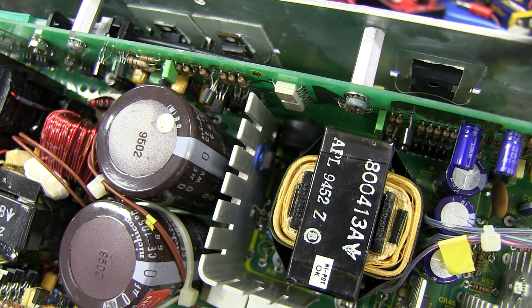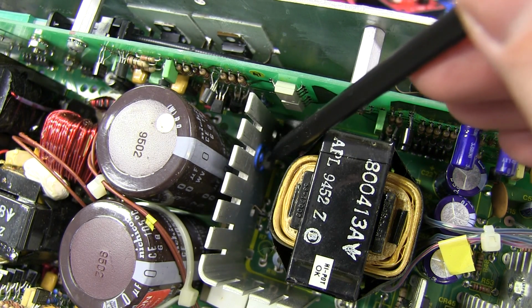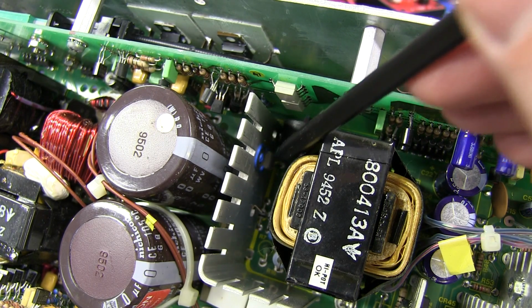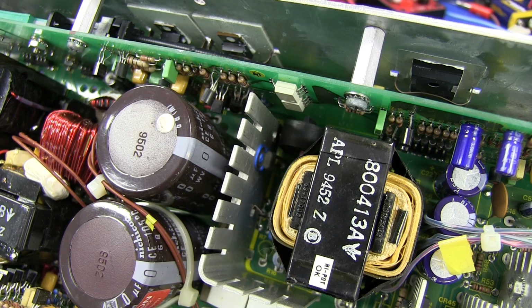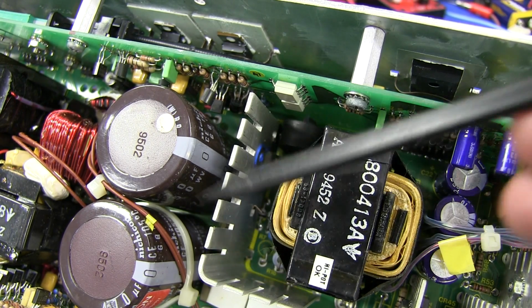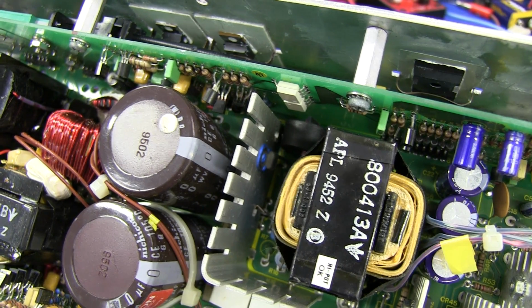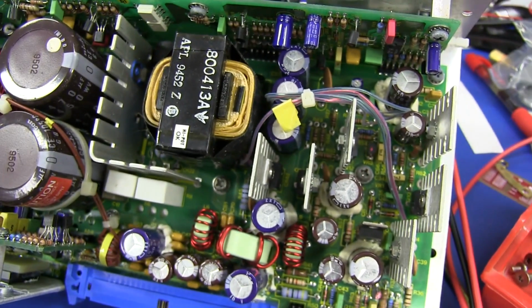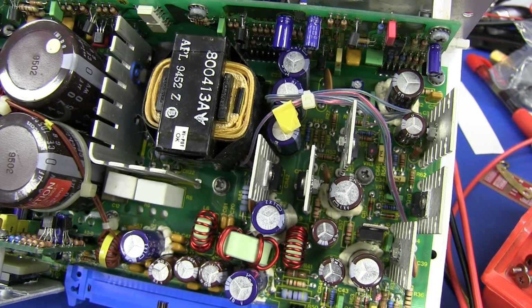You can see small attention to details like the temperature sensor down on that heatsink there. So they've got some over temp protection on that switching transistor there with that relatively small internal heatsink. Very nice. I can't find any internal fuses in this. Doesn't look obvious. I don't have a schematic of this, by the way. And the service manual for this DSA does not include the schematics. It's got extensive troubleshooting and a block diagram and everything else, but doesn't have the schematics of the main unit, let alone this third-party power supply. So I don't know. Something's gone.